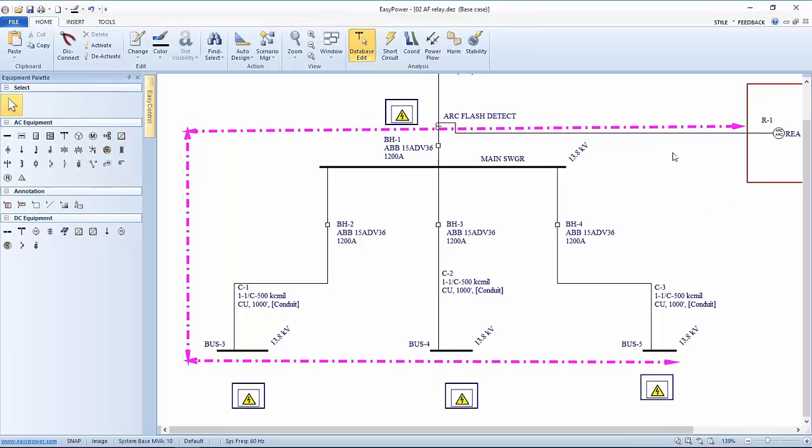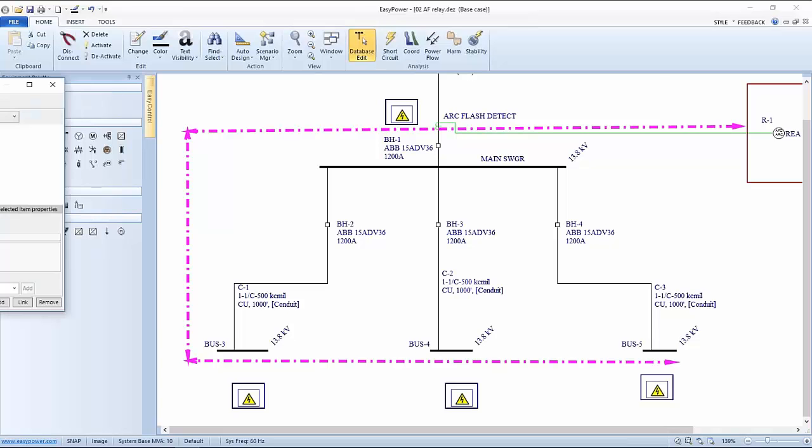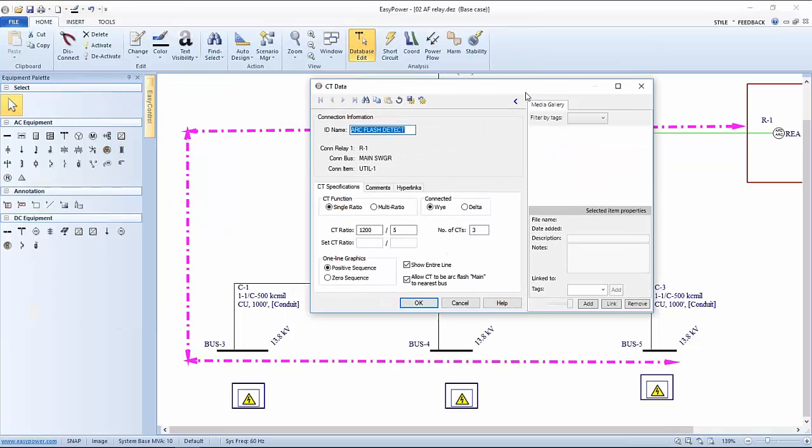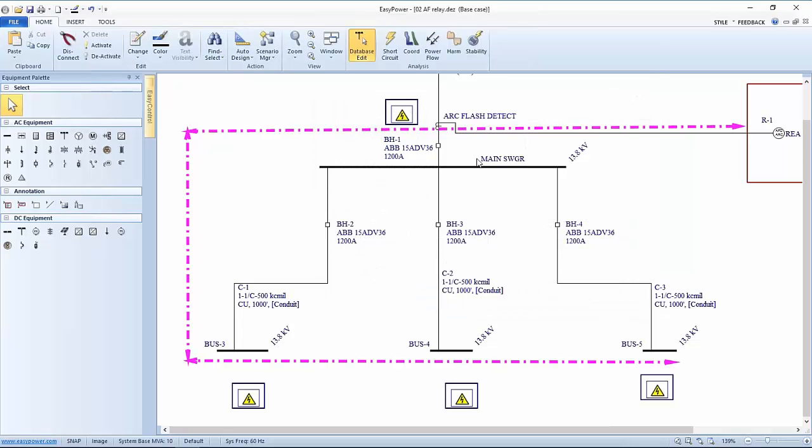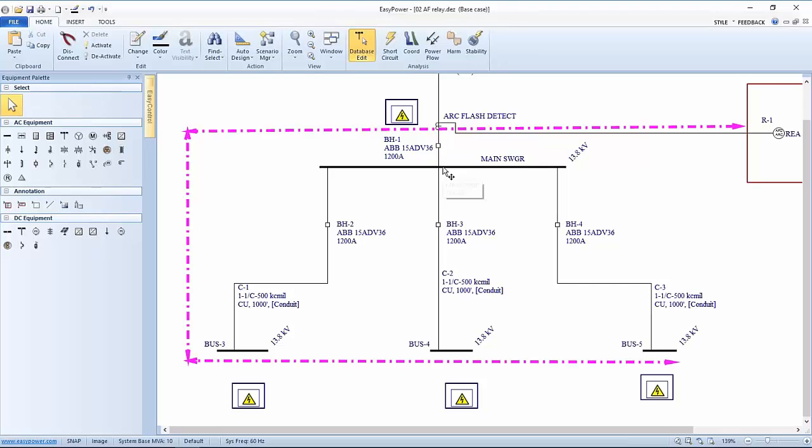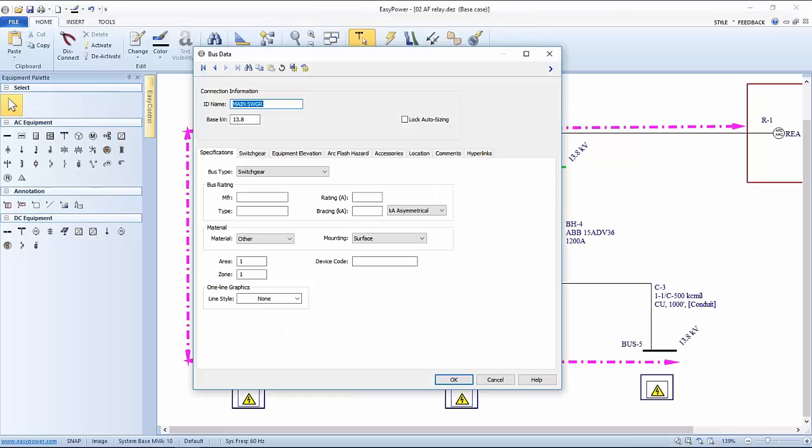In my orientation here, as I set my system up, I put a light sensor at each one of these buses. And what my legend is going to describe is the ability to take each one of these, or at least activate any one of these four sensors in terms of activating the relay. That's how I'm essentially setting it up. In essence, this CT is not really in the system if I don't have a minimum current detection. I put in Arc Flash Detect as just an indication of what this whole contraption is trying to convey.